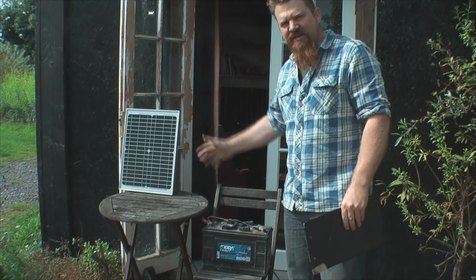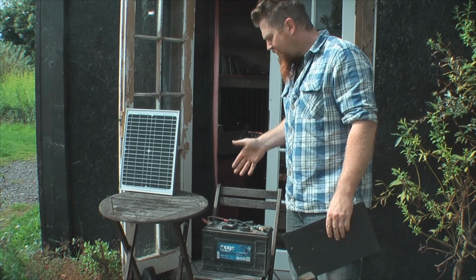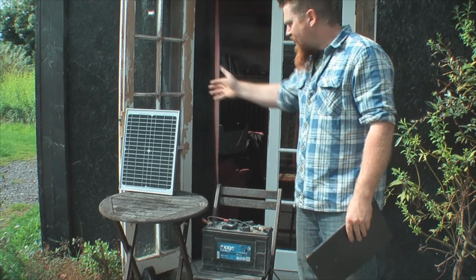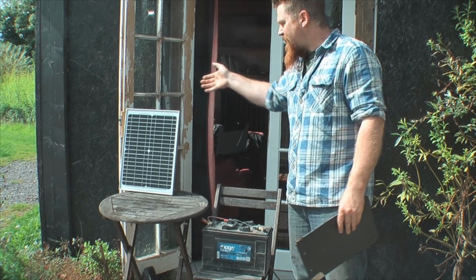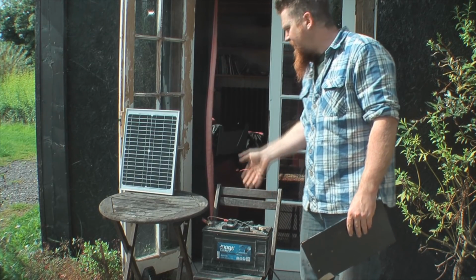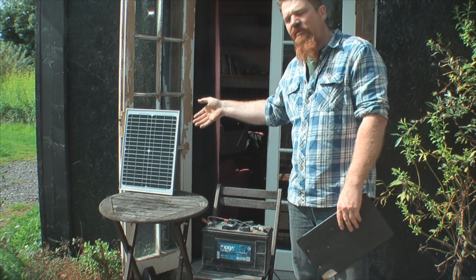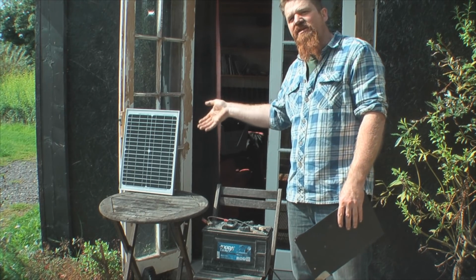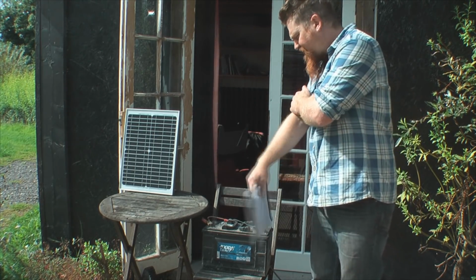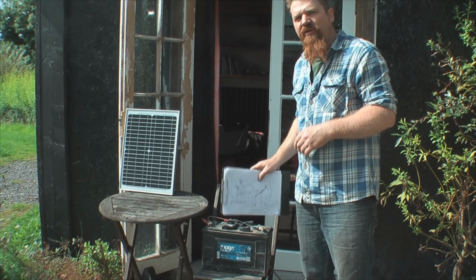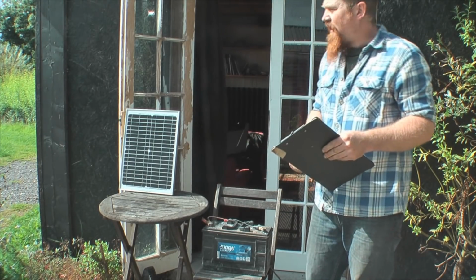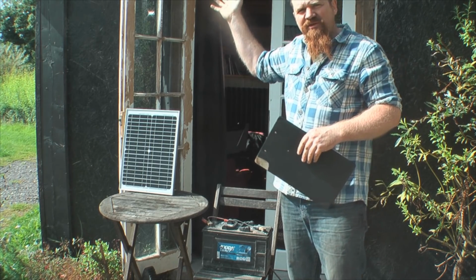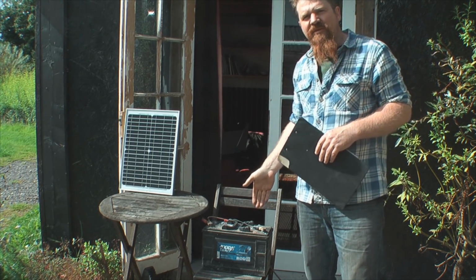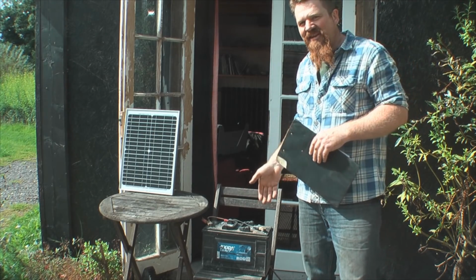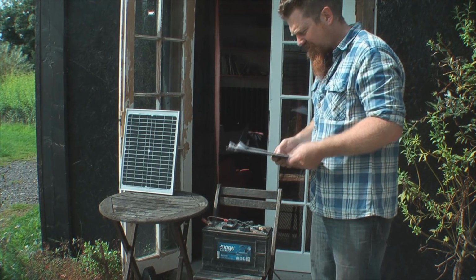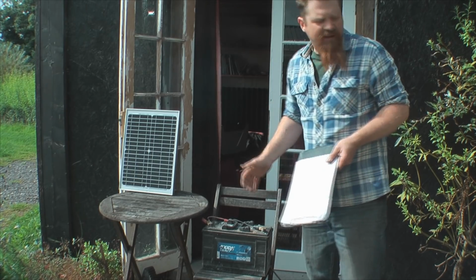This is the most basic setup then. We've got a panel directly onto a battery. Now this works, and it only works because the panel is so small compared to the battery. The panel can put out just over an amp at its best, in direct sunlight under optimum conditions. This is quite a hefty truck battery, and that can cope with that. But if I had something like panels on the roof hooked straight up to this battery, it would boil it dry quite quick. So to mitigate that...